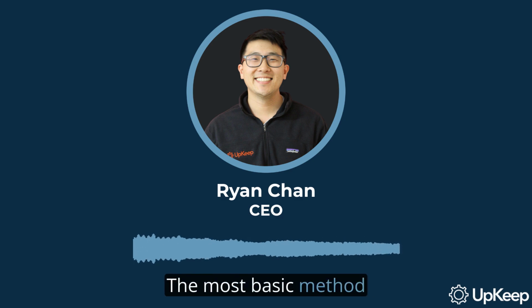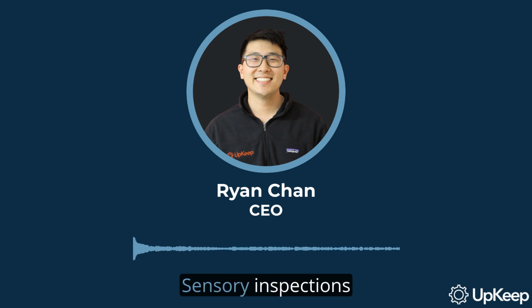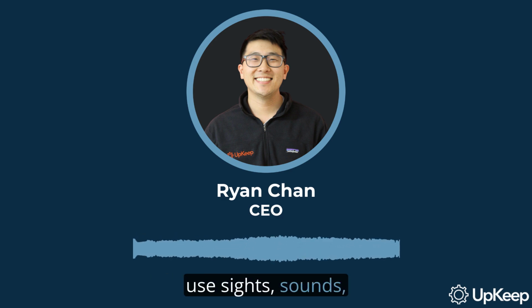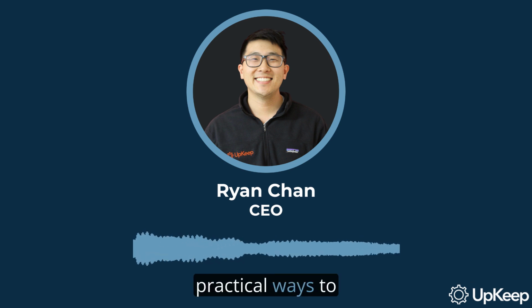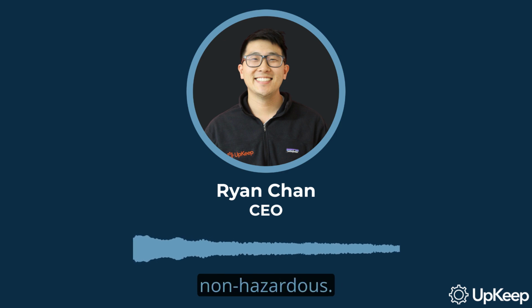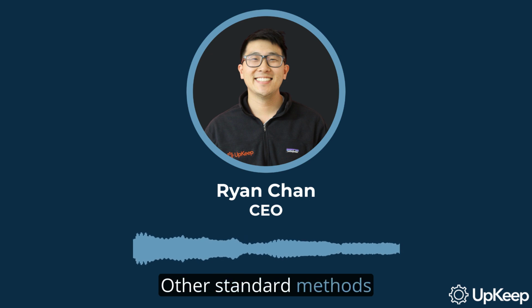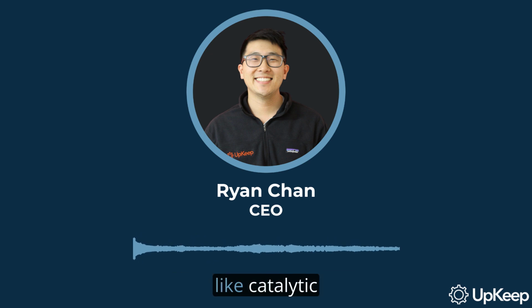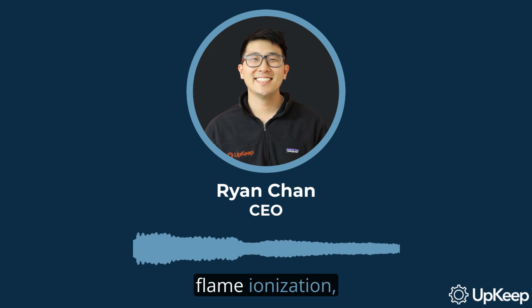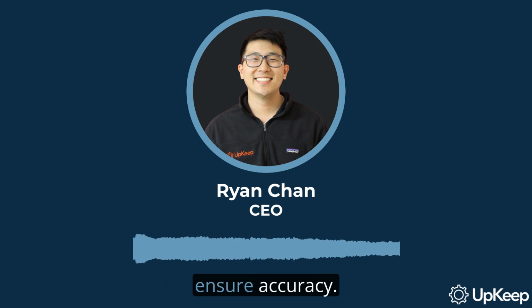The most basic method involves just the senses. Sensory inspections use sights, sounds, and smells as practical ways to detect leaks, especially those that are easily recognizable and non-hazardous. Other standard methods include the use of detection instruments like catalytic oxidation, flame ionization, and infrared absorption. These instruments are calibrated to a gas of precisely known concentration to ensure accuracy. For more sensitive measurements, newer technology allows for optical gas imaging to safely detect industrial gas concentrations.